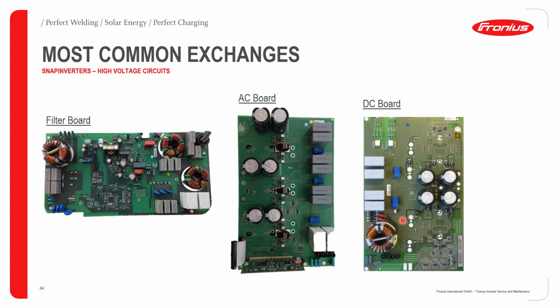Also looking at the DC board. The DC board basically takes the DC from the filter board and then either steps up or steps down the DC voltage in order to make sure that it falls within the MPPT tracking range.